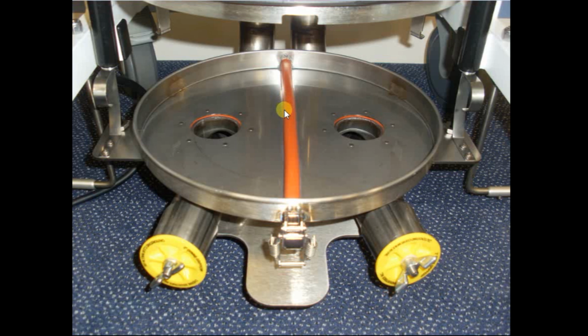And what you see here, this orange seal here, is a seal between the absorber pan tray and the soda lime canister. Now this seal has no bearing or effect with regards to leaks in the patient circuit. It merely stops gas passing from this side of the circuit to this side of the circuit and prevents it going across there rather than going up and through the soda lime.